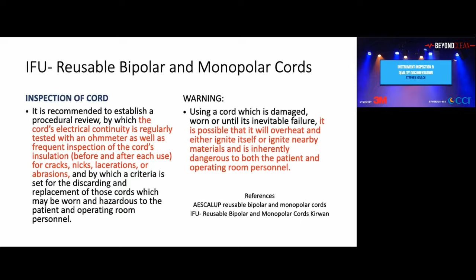There's a potential for the cord to spark and cause fire. During a laparoscopic procedure, the Bovie was not working. How many of us have been in a procedure where they say, turn up the coag, turn it up 5 more, turn it to high, no turn it up, I can't cut, I can't do it. There could be something going wrong. Maybe the tip isn't clean, but it could be the cord. It could be the wire inside the cord.